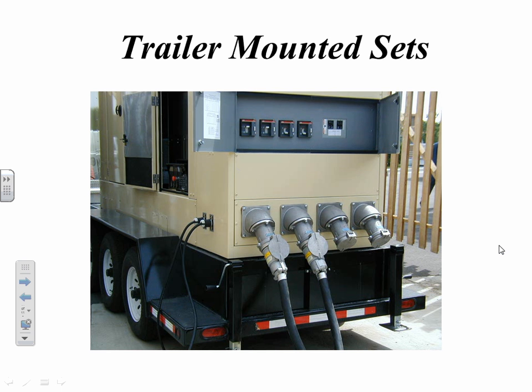That's a lot. I'll give you a little thing that I've used over the years. One of the old buggers that mentored me told me, if you can divide the high side and the low side voltage by 120 evenly, it's a delta configuration. If you can't, it's a Y. Real simple thing, but it's true. 120, 240, 3 phase, that was the first one I drew. That's a delta.